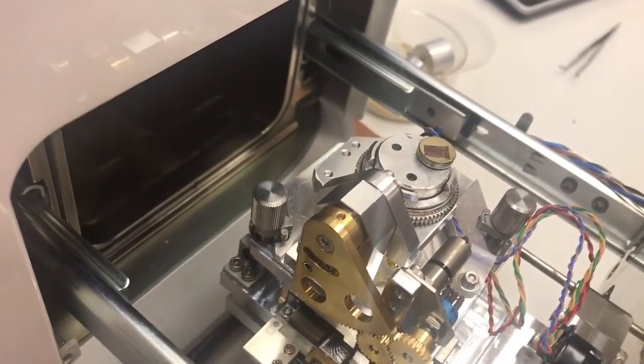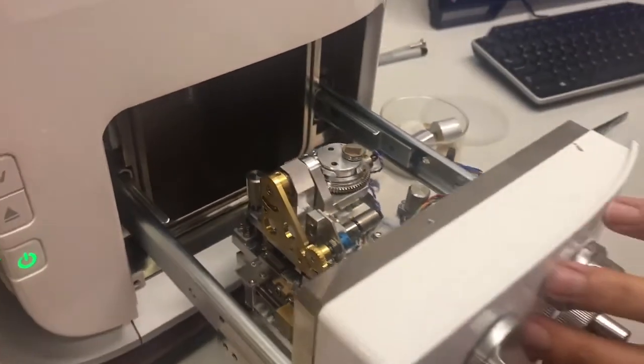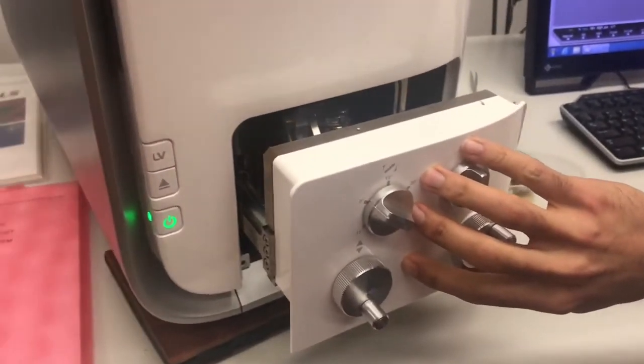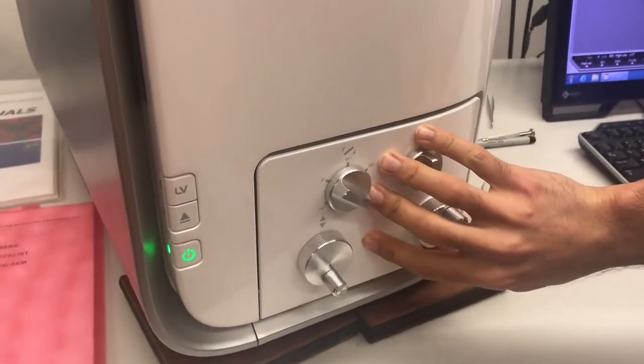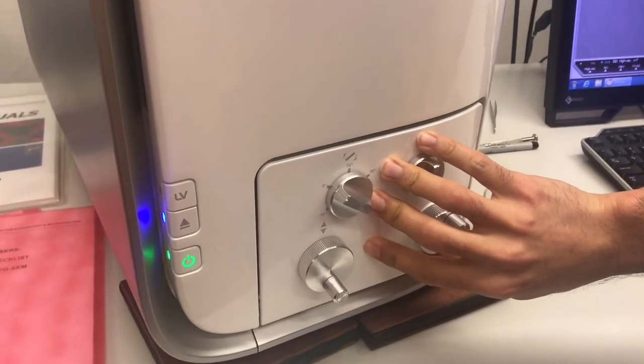Once the sample has been positioned correctly, you can close the door. While closing the door, watch and make sure the sample height is lower than the chamber. Push firmly on the door until you hear the pump start, and continue holding for 5 seconds until the vacuum holds the door closed.